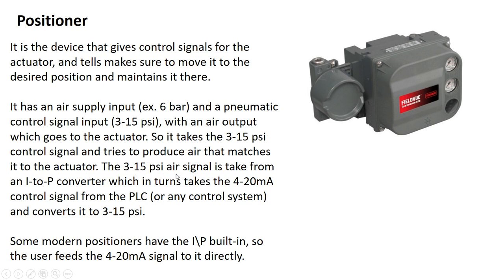The 3-15 PSI air signal is taken from the I2P converter, which in turn takes the 4-20 mA control signal from the PLC or any control system such as a DCS, and then converts it to 3-15 PSI. The I2P converter is the current-to-pressure converter — it takes the industry standard 4-20 mA current signal and converts it to the 3-15 PSI air pressure signal that the control valve positioner accepts. Some modern positioners have the I2P unit built in, so the user just feeds the 4-20 mA signal directly.